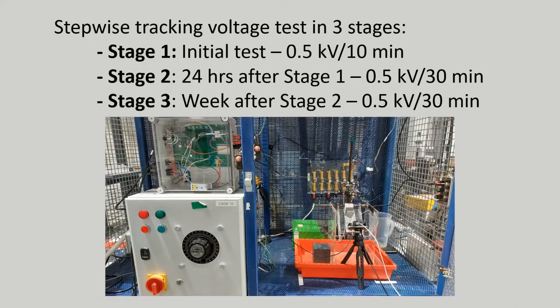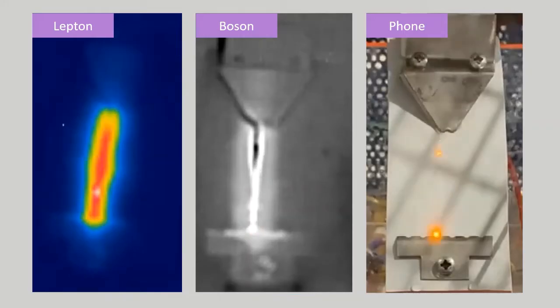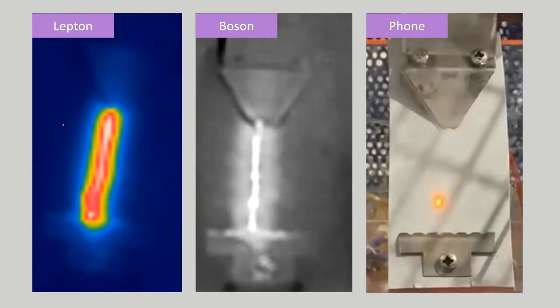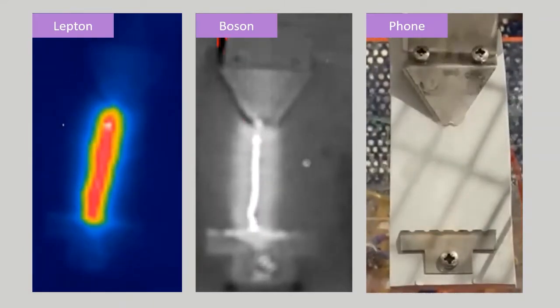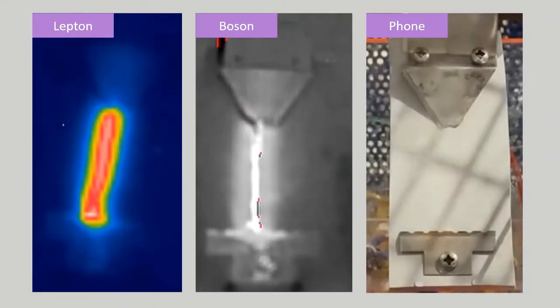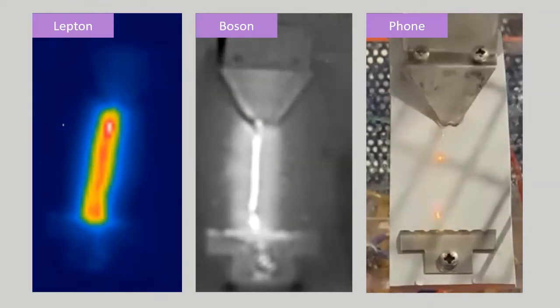To investigate the performance of the coated insulators, a stepwise voltage tracking test was conducted in 3 stages. Stage 1, the initial testing. Stage 2, conducted 24 hours later, and Stage 3, a week later. Measurements of the contact angle were taken following each test and just before Stage 3. The results from the thermal cameras provided a deeper insight into the formation of conductive paths along the insulator surface, in particular how and when they are formed.